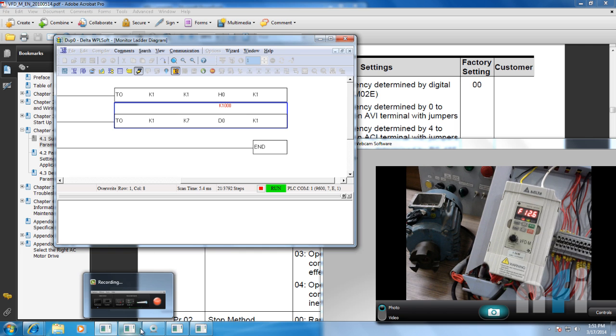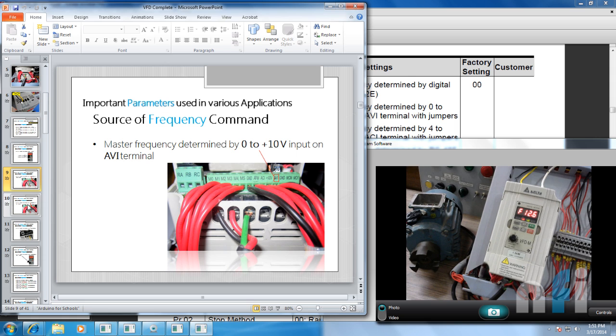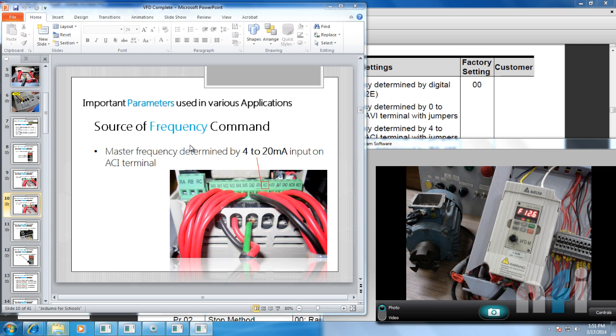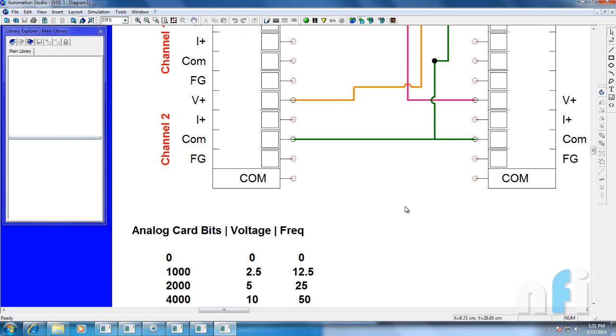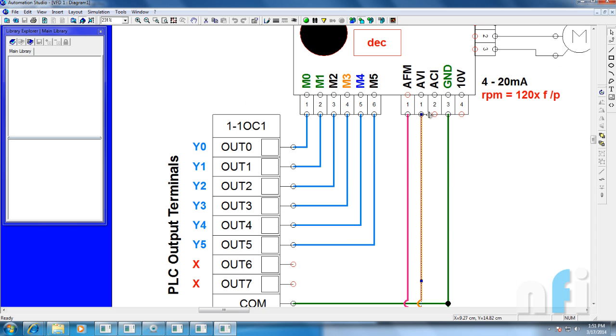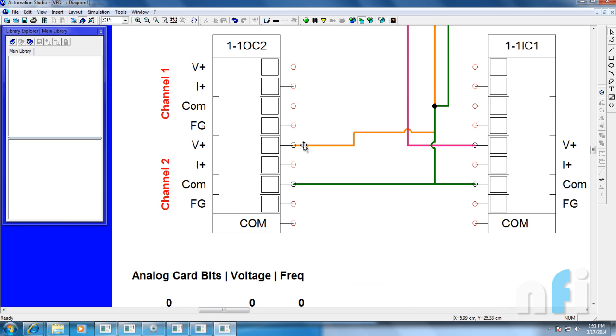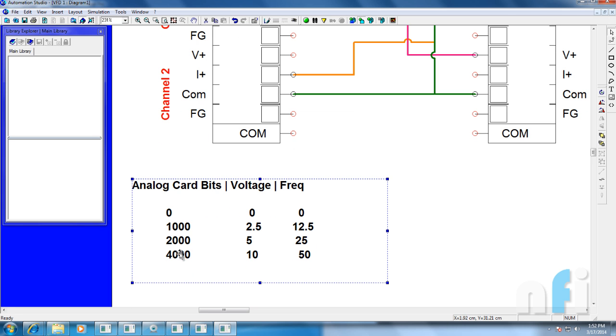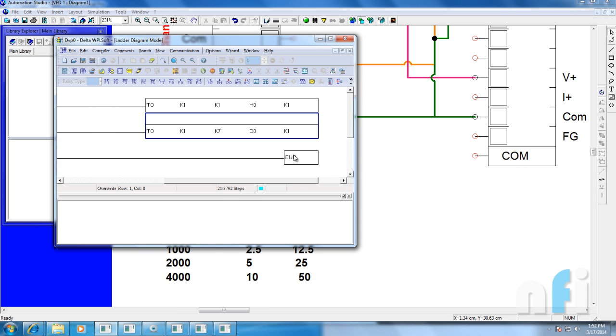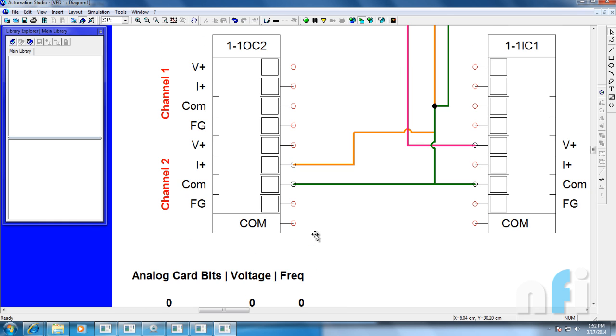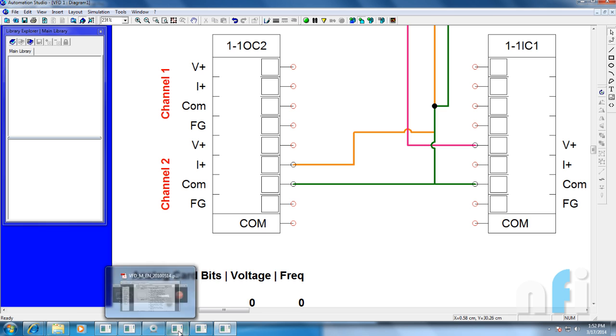That was about changing the frequency by AVI terminals — 0 to 10 volts at the AVI terminal. The next option is master frequency determined by 4 to 20 mA on ACI terminal. For ACI, we just have to connect the AVI wire to ACI and switch the terminal from V+ to I+, because I+ will give 4 to 20 mA. The bit range is the same — 0 to 4000 — just the output changes from 0–10 volts to 4–20 mA. So it's quite similar; you just need to change the source to current.